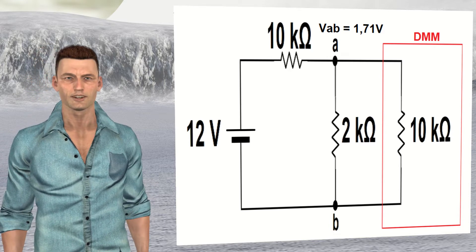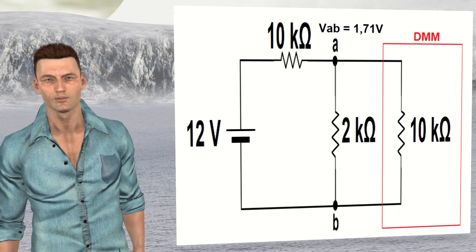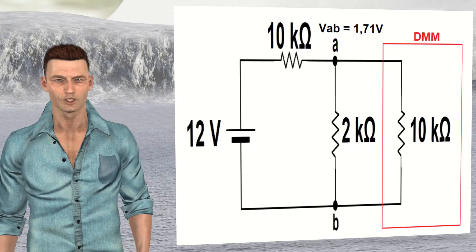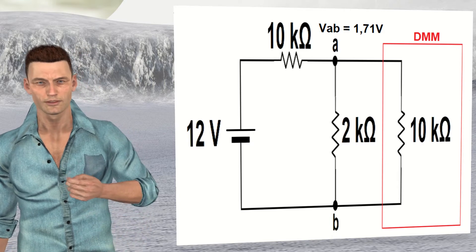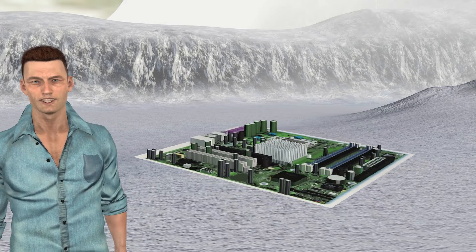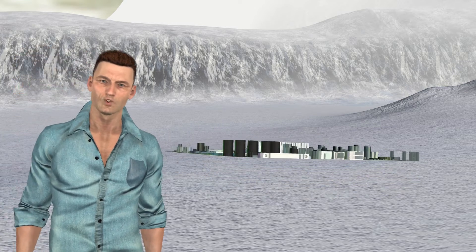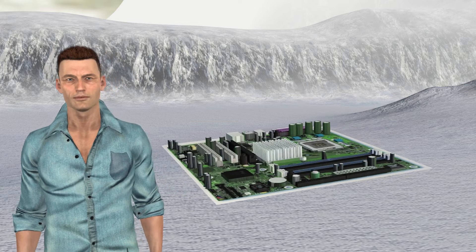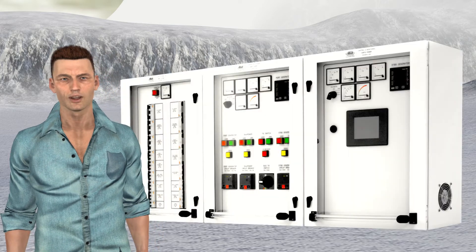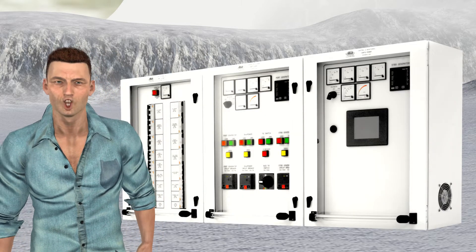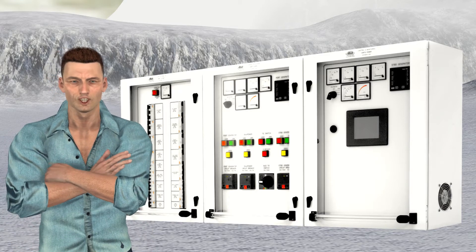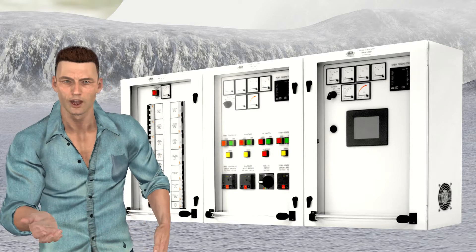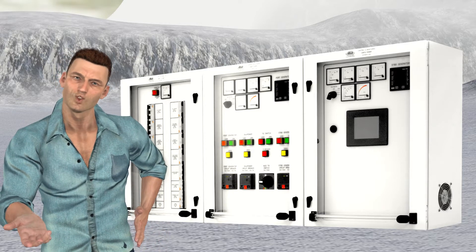We see in this way that the lower the impedance of a multimeter, the greater the impact it has on the circuit, altering the value of the voltage that the circuit has when the voltmeter is not applied. For this reason, in sensitive electronic circuits it is important to use multimeters with a high input impedance to avoid altering the electronic signals. For electrical distribution systems, the effect of using a voltmeter with a low input impedance is negligible — that is the reason why in many electrical distribution cabinets we find analog voltmeters that generally have a low input impedance.